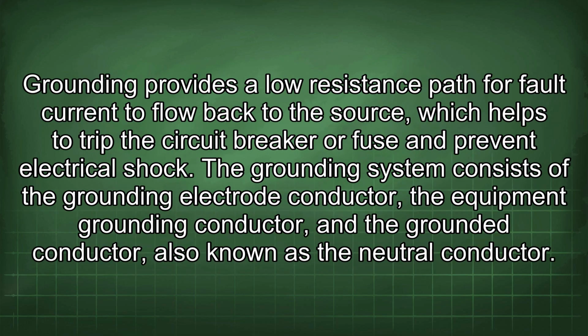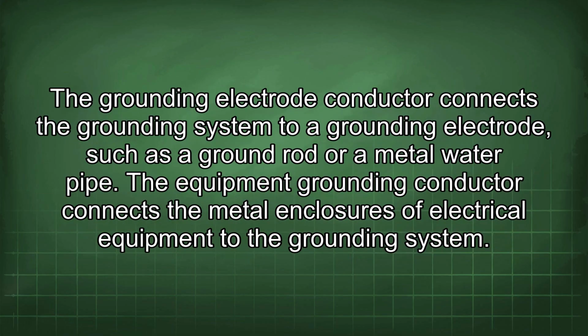Proper grounding is another critical aspect of electrical safety. Grounding provides a low-resistance path for fault current to flow back to the source, which helps to trip the circuit breaker or fuse and prevent electrical shock. The grounding system consists of the grounding electrode conductor, the equipment grounding conductor, and the grounded conductor, also known as the neutral conductor. The grounding electrode conductor connects the grounding system to a grounding electrode, such as a ground rod or a metal water pipe.